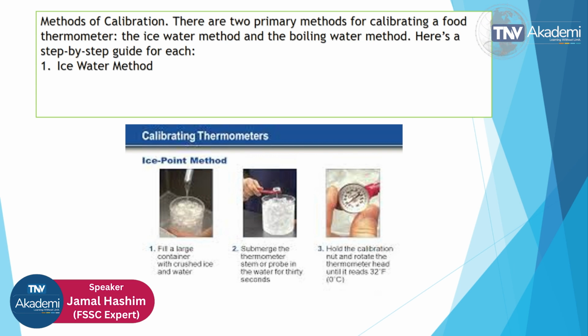Procedure: prepare ice water. Fill a glass with crushed ice and add clean water to the top. Stir well. Let it sit for a couple of minutes to stabilize the temperature at 32 degrees Fahrenheit or 0 degrees centigrade. Now insert the thermometer. Insert the probe of the thermometer into the center of the ice water, not touching the sides or bottom. Stir gently to ensure an even temperature around the probe. Wait for stabilization. Wait for the reading to stabilize, about 30 seconds to 1 minute. Check the reading. The thermometer should read 32 degrees Fahrenheit or 0 degrees centigrade. If not, it needs adjustment.